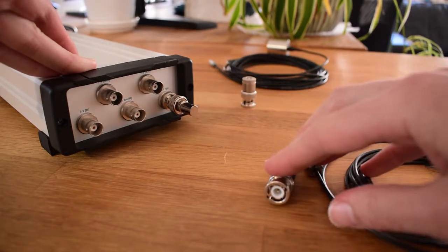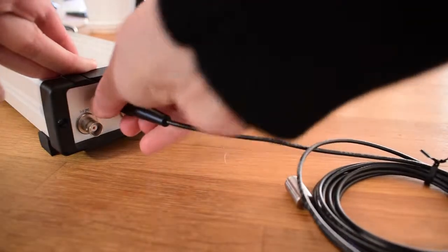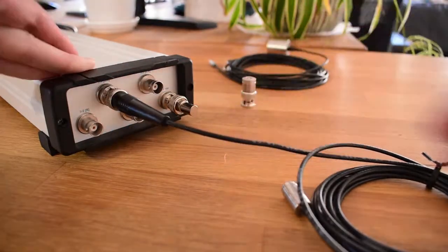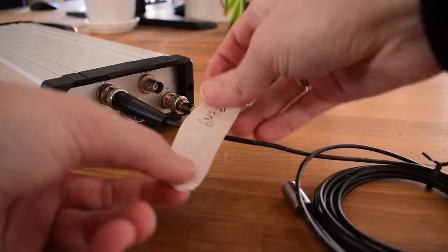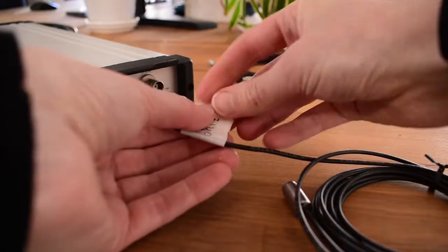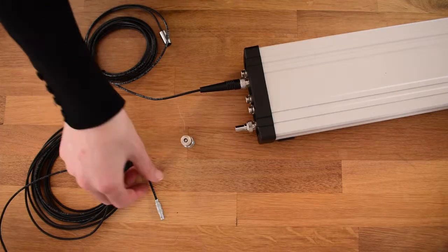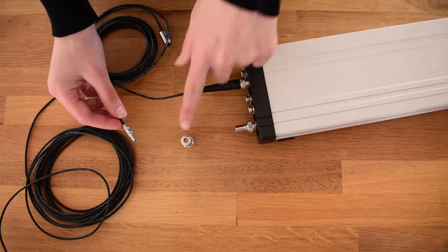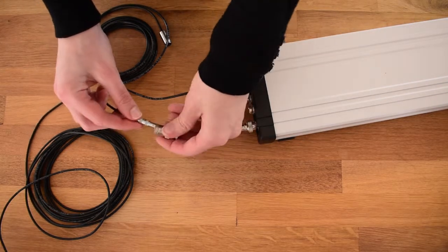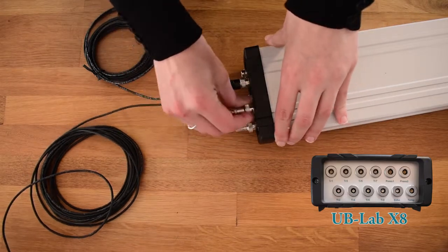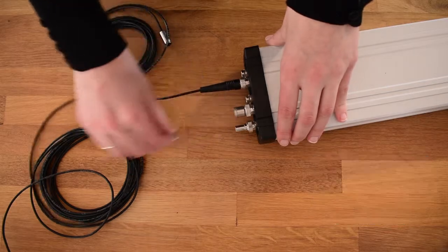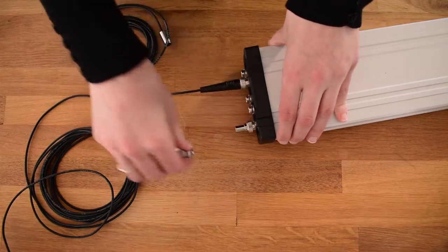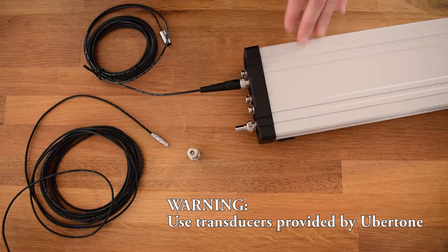Remembering which transducer is plugged in which channel is essential. A tip is to tape the information on the connector side. Like this. Here it's a 6 MHz transducer, and here you go. If you have transducers with LEMO connectors, you can simply purchase an adapter and plug it in between. Those LEMO connectors are compatible with the UB Lab X8. Big warning, the device can be damaged if you use transducers with very low impedance. So if you want to use transducers which were not provided by Ubertone, please check with us before.